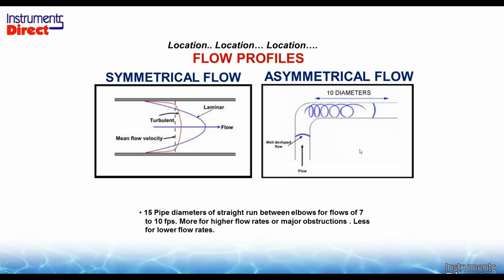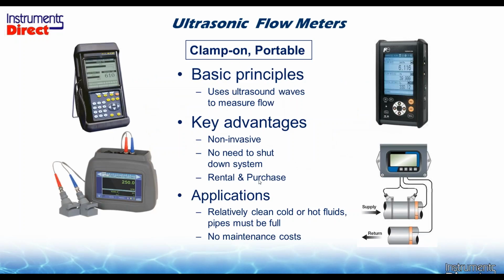With a short straight run application, we call that an asymmetrical flow profile. For example, I'm coming up this elbow here. In this turn, this is a shorter distance and this is a longer distance. You're going to get a tumbling effect at this point. If you were to put your ultrasonic transit time flow meter here, you'd probably get a fault condition, and you probably wouldn't get anything at all. You need to go downstream 10 pipe diameters and put your sensor there, with another 5 on the other side. When you have this situation, you have optimum performance with your ultrasonic transit time flow meter. Now, it comes in many different shapes and configurations. There's a variety of portable devices out there, there's a variety of dedicated devices, and there are some limits.